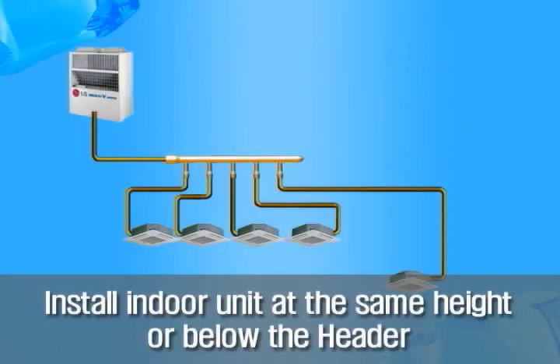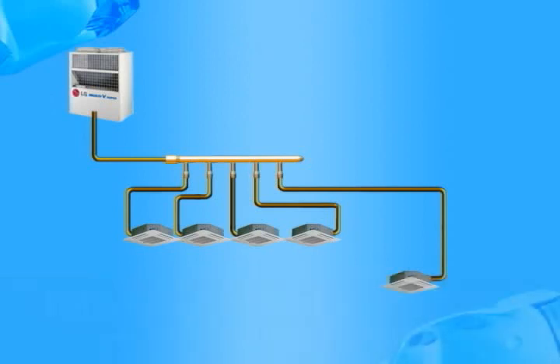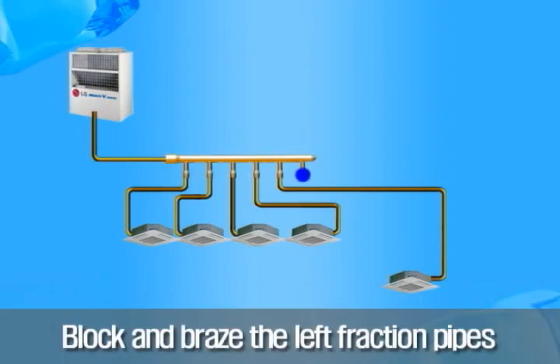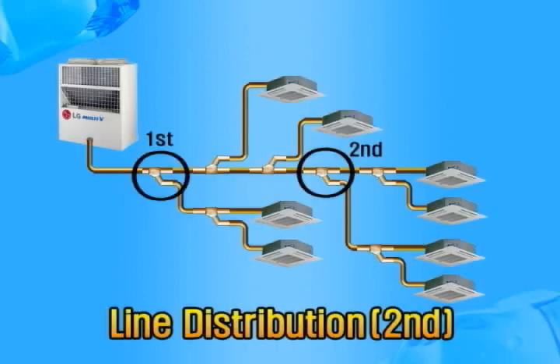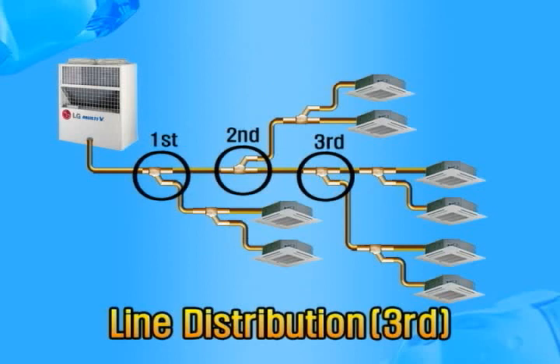Install the indoor unit at the same level as or below the header level. To minimize the capacity differences of the indoor units, make sure the difference in the length of the branch pipes is minimal. Also, the indoor unit with bigger capacity is recommended to connect closer to the outdoor unit. After the connection, block and braze the remaining branch pipes to prevent leakages. The following are examples of refrigerant distribution.